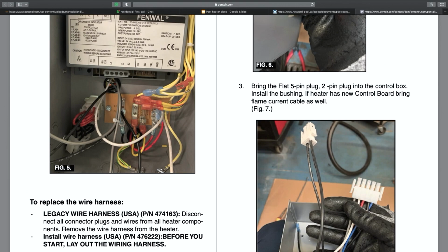If my temperature is set at 95, when they turn their controller on, this heater's gonna turn off at 95. And so this will also be in the install description, there'll be a warning about that. And so you go in there, just turn this fireman hookup up to max temperature, and then the external controller with its own thermostat just brings the heater on and off as needed.